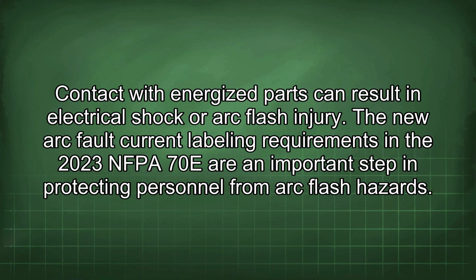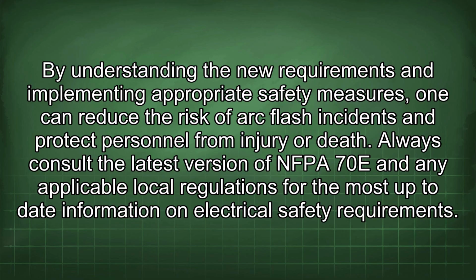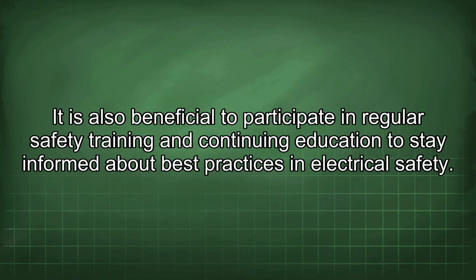The new arc fault current labeling requirements in the 2023 NFPA 70E are an important step in protecting personnel from arc flash hazards. By understanding the new requirements and implementing appropriate safety measures, one can reduce the risk of arc flash incidents and protect personnel from injury or death. Always consult the latest version of NFPA 70E and any applicable local regulations for the most up-to-date information on electrical safety requirements.